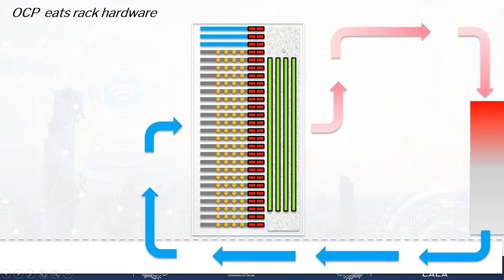Also in the back of the rack, you've got all the cable spaghetti. Then the hot air comes out the back, goes over the top and down into what we call a downflow CRAC unit, a computer room air conditioning unit, which uses mechanical chilling and refrigeration, passes the cool air under the floor and then back up to the front.